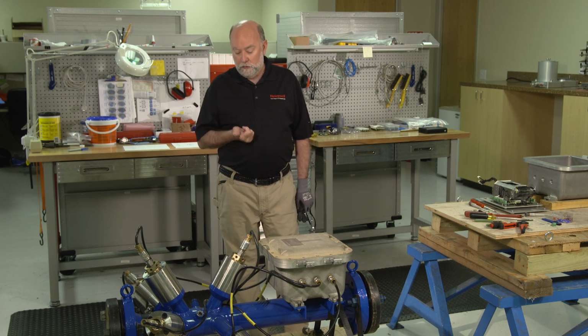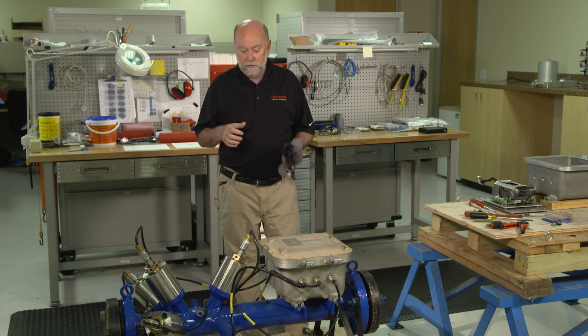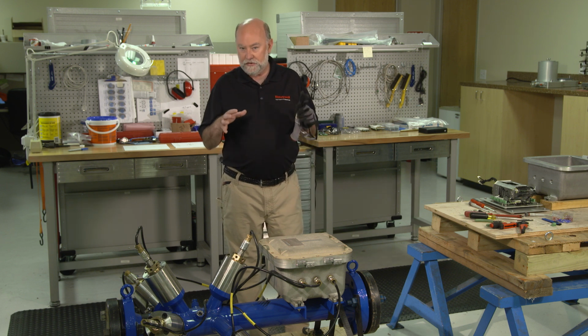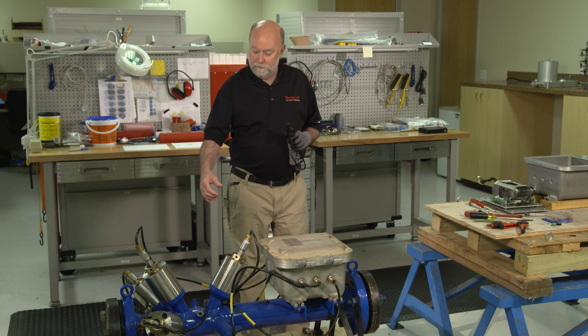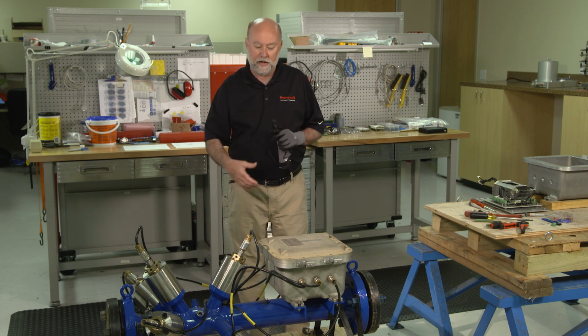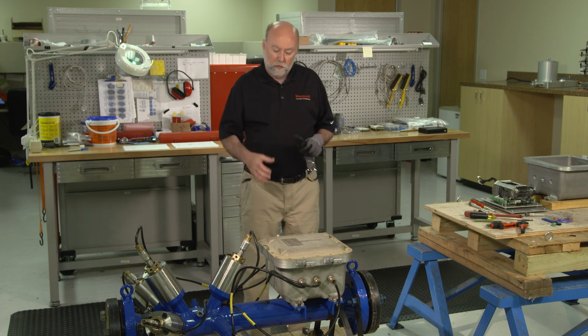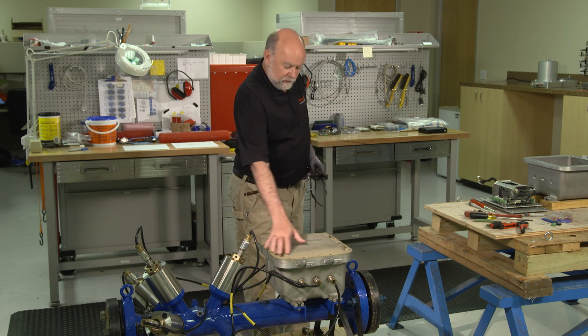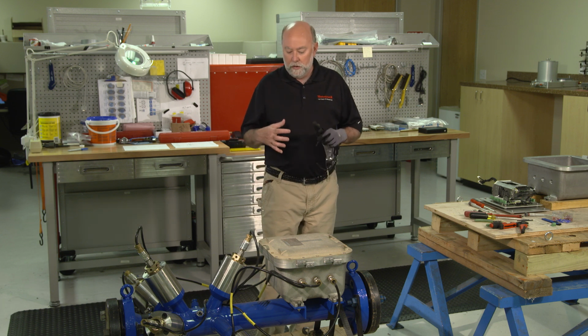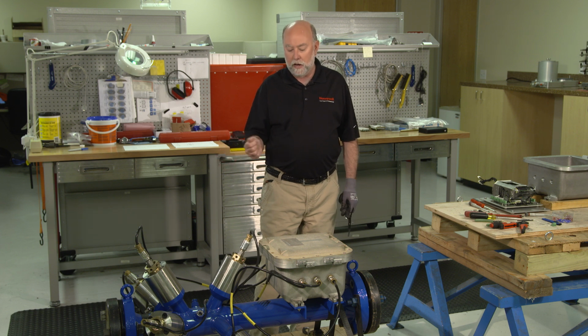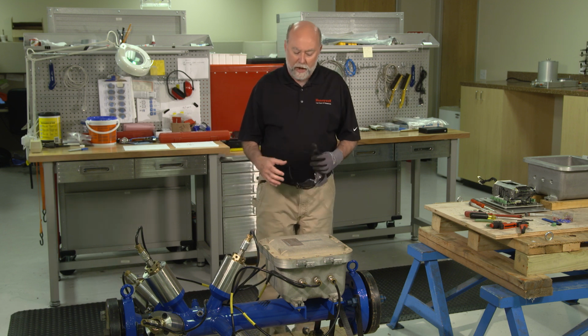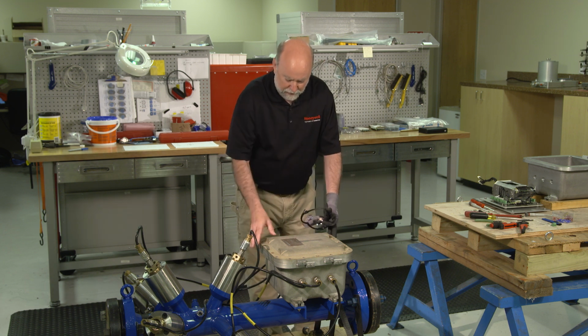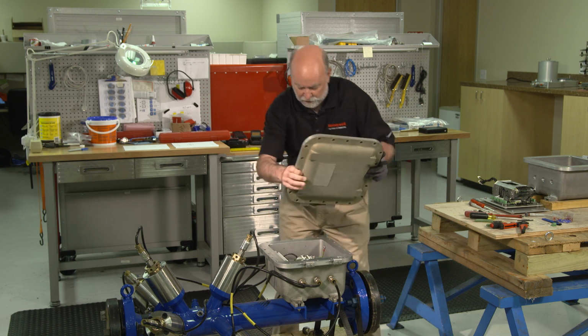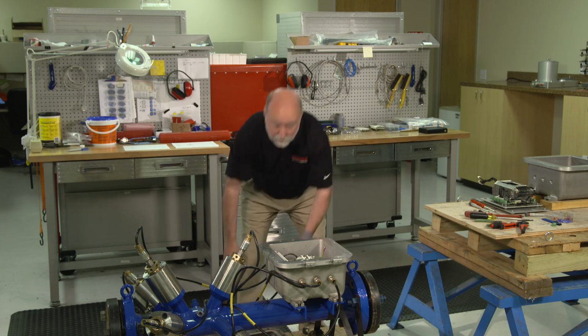But if you can't depressurize the meter, you would like to try to make it as safe as possible, maybe by removing any pressure tubing connections, that sort of thing. Before we can even open up this explosion-proof box, where we've already removed the bolts, in the real world, in the field, you're going to need to de-energize all the circuits that come into and go out of this box so that it's safe for you to work on. Once you've done that, then we would open this box up. Again, we've removed the bolts so that we can take this lid out of our way.